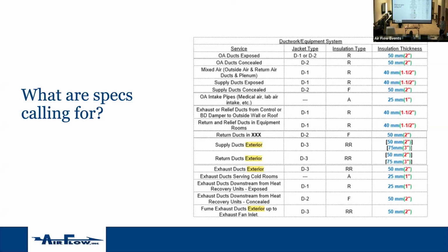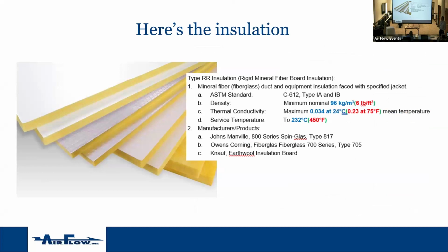Yeah. So we've got supply ducts exterior, so they're talking about a jacket type D3 and insulation type RR, which I assume is rigid. And then the thickness of the insulation, it should also be an R value. So here's what it was, R rigid mineral fiber board. So they're taking these rigid boards, and you saw that they got notched in order to make it around the bend, and there's often a lot of bends. If it's all square elbows, maybe this isn't that big of a deal, right?